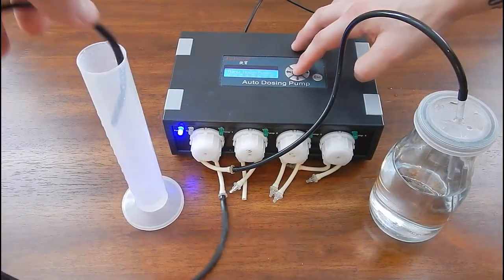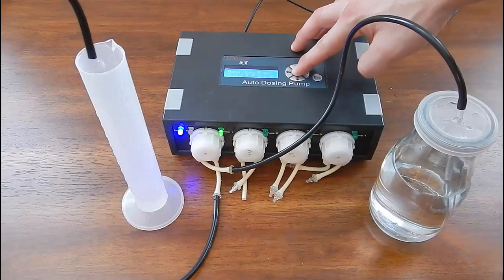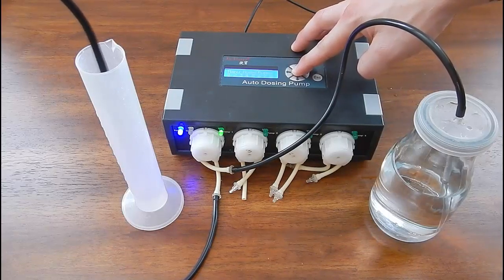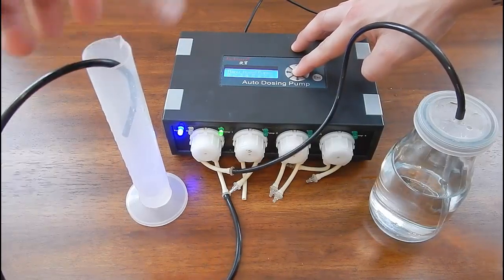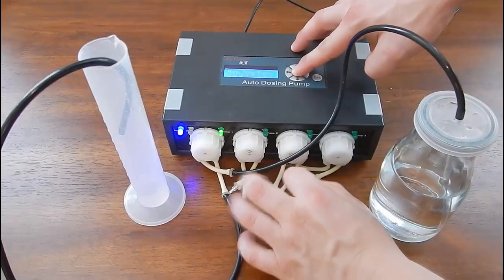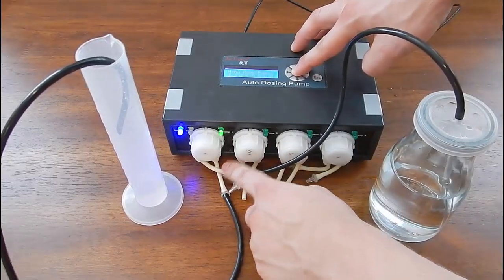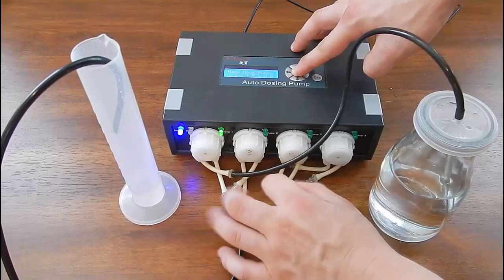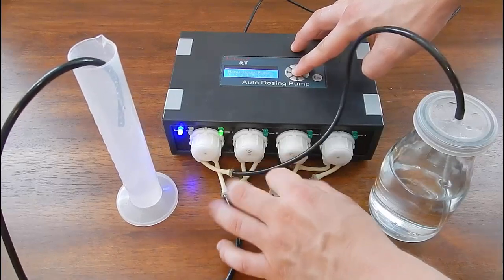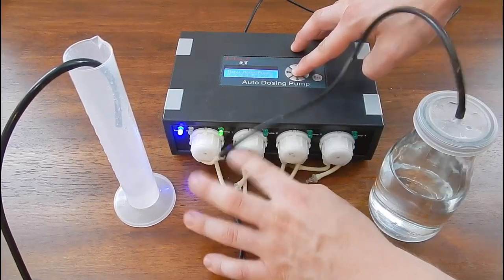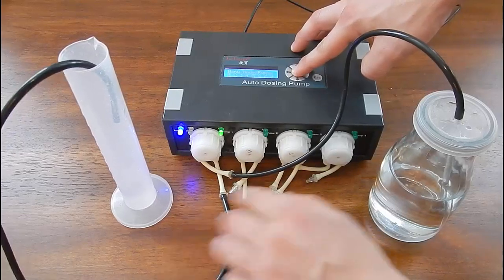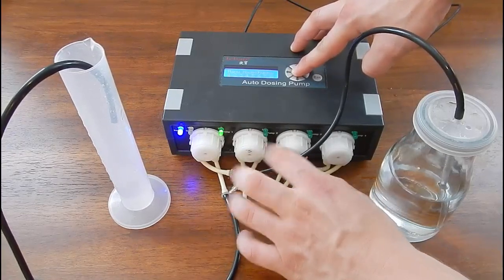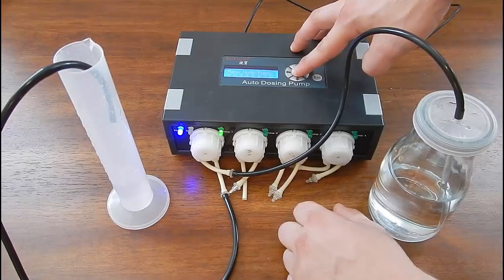Okay, let's go ahead and run the pump. As you can see, there's water coming out right now. Just set that down in the cylinder. Usually the air bubbles get trapped up in the pump head itself, so just give it a couple flicks. I usually let it run for about 100 milliliters just to make sure all the air bubbles are out. That's how you bleed the line.